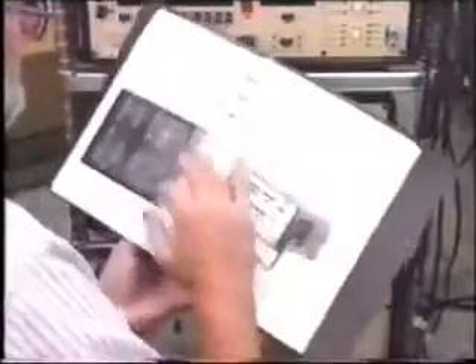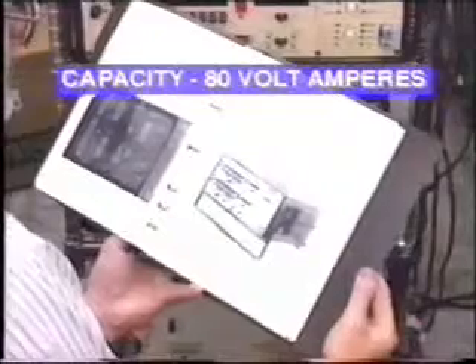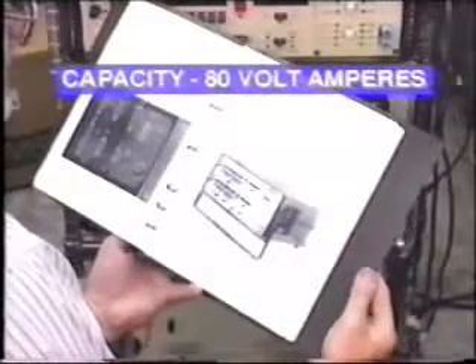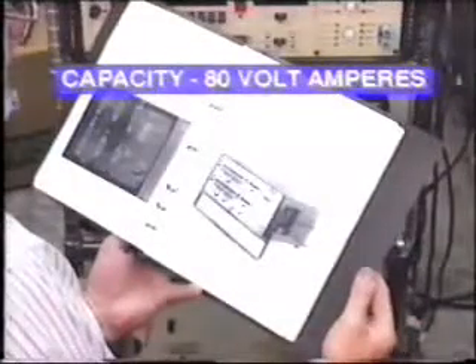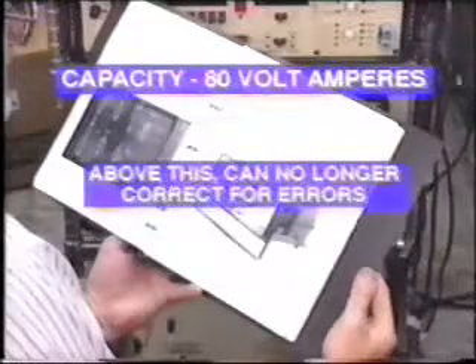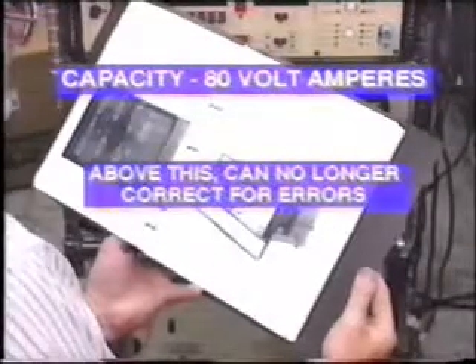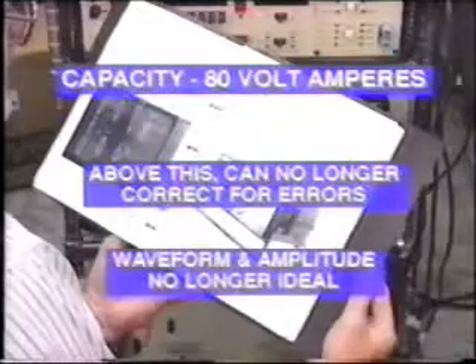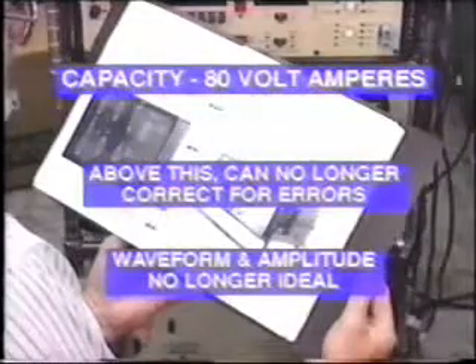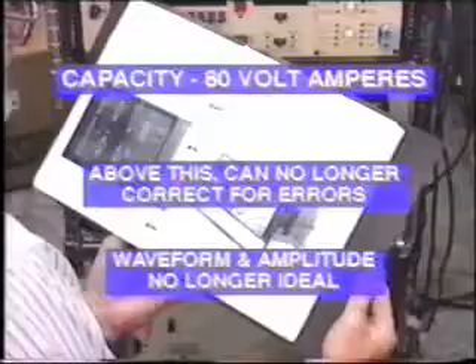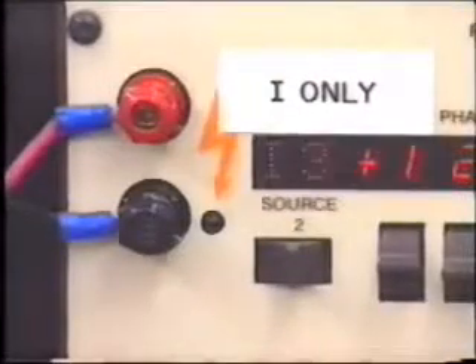The instruction book tells us that the voltage source can deliver up to 80 volt amperes. This means that once the limit of self-regulation is reached, the source can no longer correct for errors, and the waveform and amplitude begins to stray from ideal values. The output falls rapidly, and the source will go into error. The test set will let us know when this limit is exceeded by beeping and flashing an ER, or error message, in the source ID window.